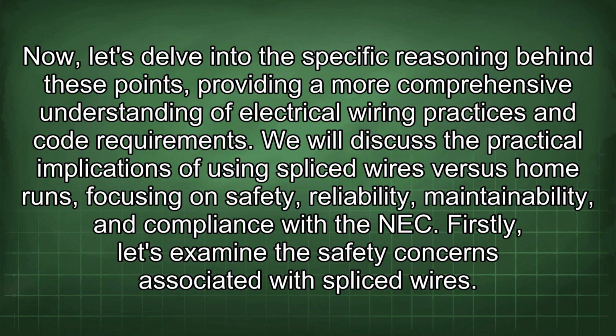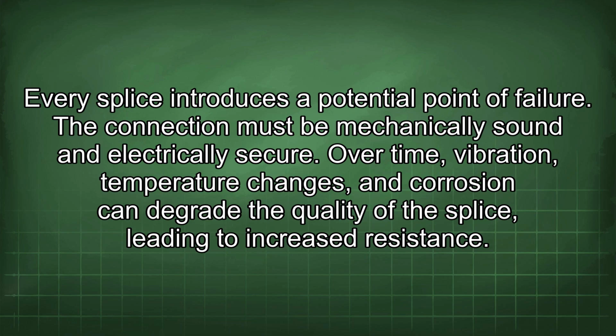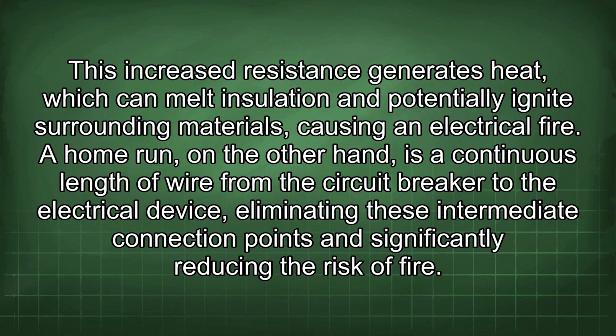We will discuss the practical implications of using spliced wires versus home runs, focusing on safety, reliability, maintainability, and compliance with the NEC. Firstly, let's examine the safety concerns associated with spliced wires. Every splice introduces a potential point of failure. The connection must be mechanically sound and electrically secure. Over time, vibration, temperature changes, and corrosion can degrade the quality of the splice, leading to increased resistance. This increased resistance generates heat, which can melt insulation and potentially ignite surrounding materials, causing an electrical fire.